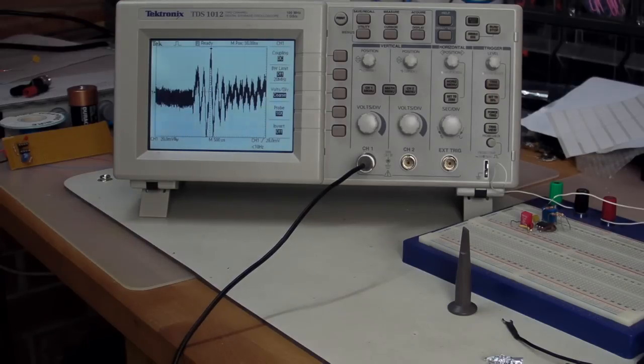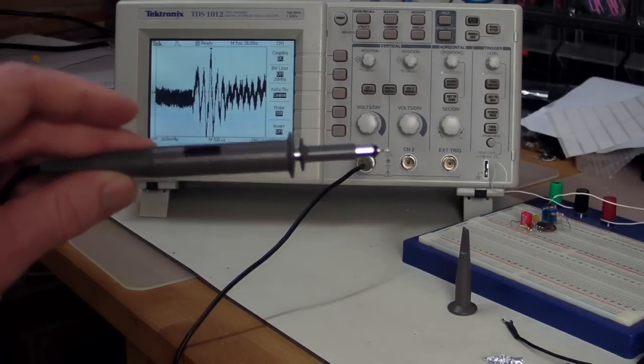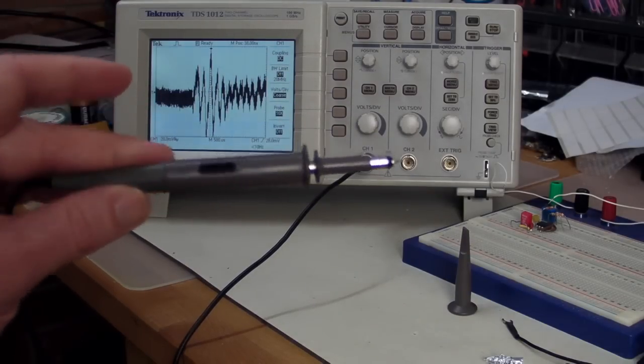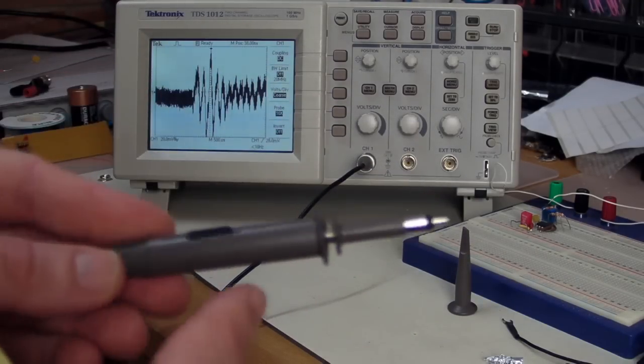So, what's causing this? Well, it's probably a little bit complex, but what it ultimately is likely to come down to are the ceramic capacitors used in these probes for compensation.